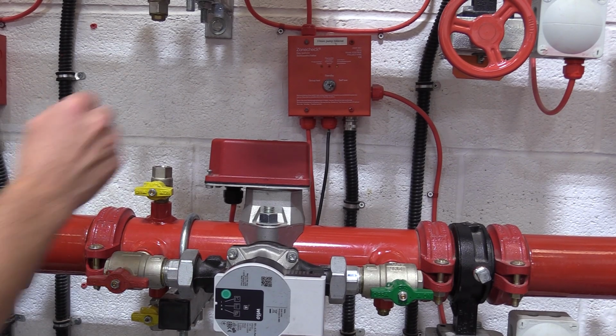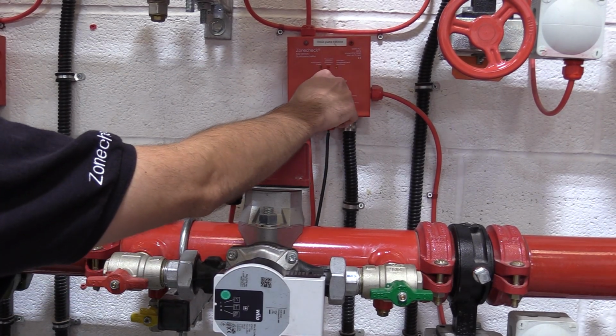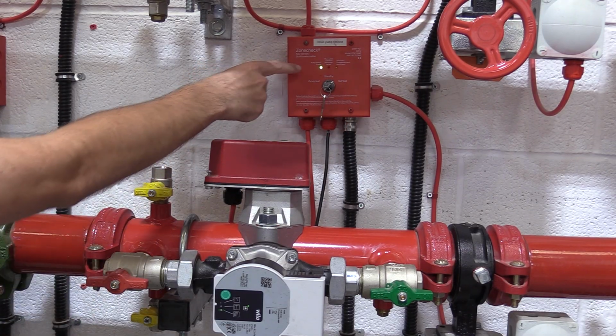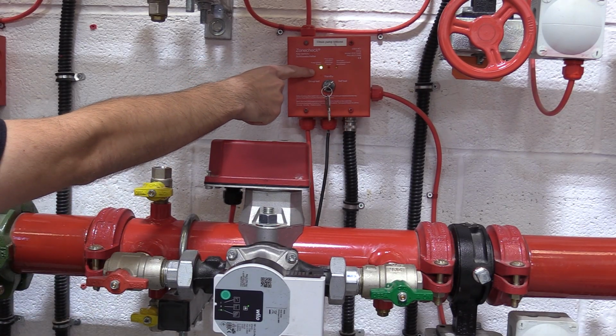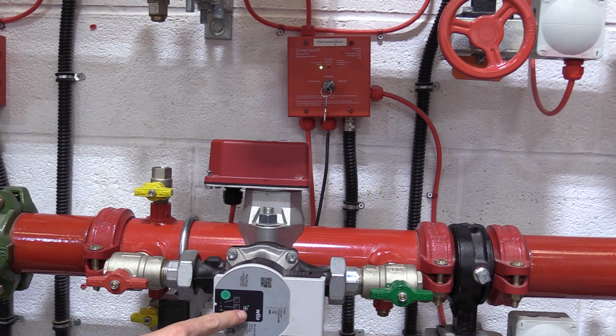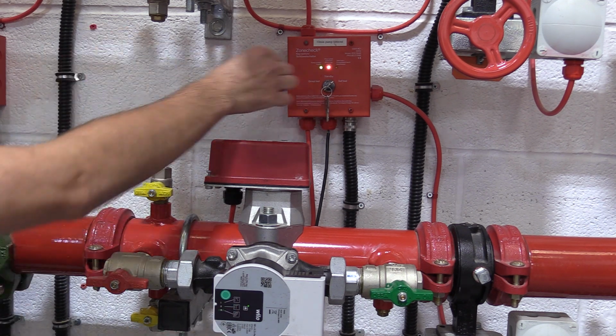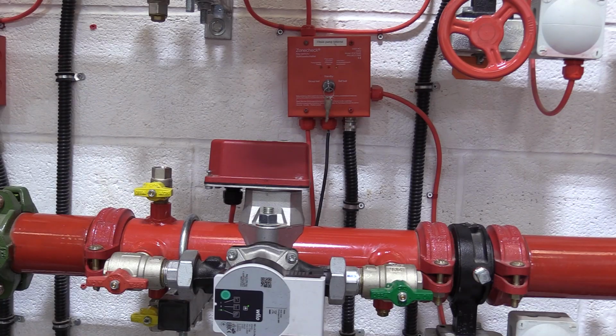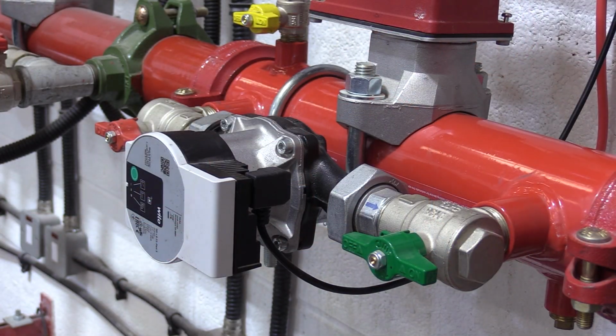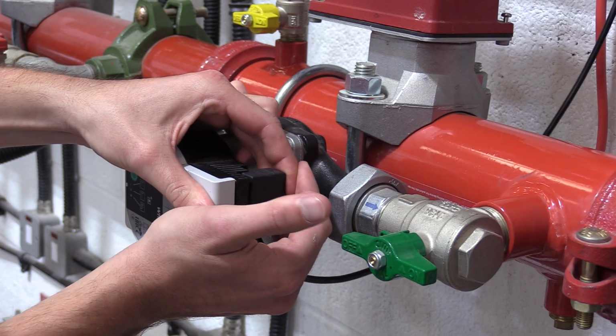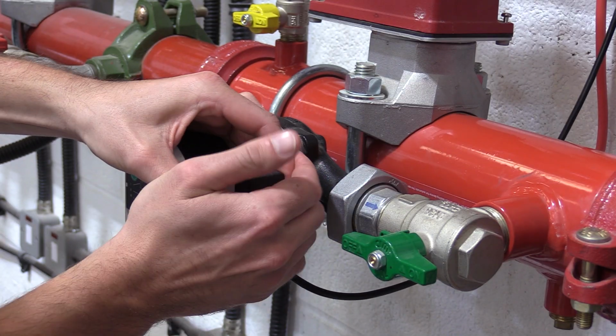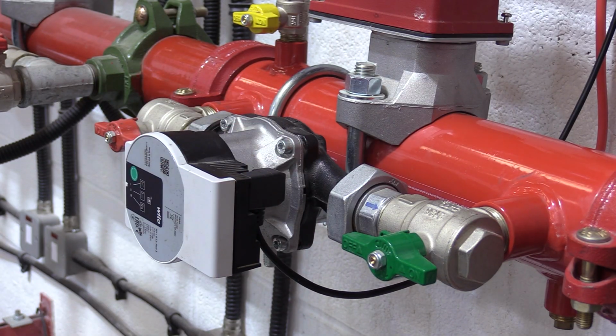Check power is available at the pump. With the key switch in the self-test position, the top LED on the pump should blink and then illuminate to show that it is powered on. If you are close to the pump, then you should be able to hear it spinning and or water moving. If no power is available at the pump, then firstly check that the pump cable is fully inserted into the pump before continuing to advanced troubleshooting electrical.